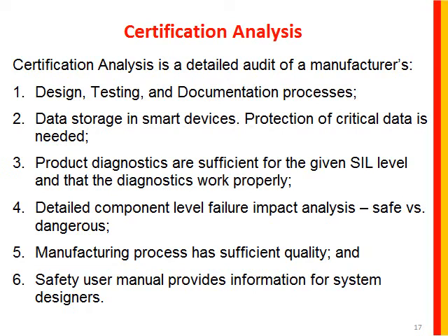The certification analysis can be summed up by saying: the certification body looks at the design, testing, and documentation process; audits data storage and smart devices; analyzes a manufacturer's product diagnostics because there are minimum levels of requirements for diagnostic coverage; does a detailed component-level failure impact analysis (the FMEDA), which generates failure rates as a function of failure modes — safe and dangerous; audits the manufacturing process quality; and audits the end-user documentation.